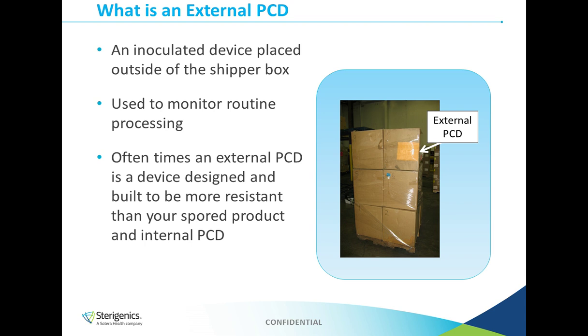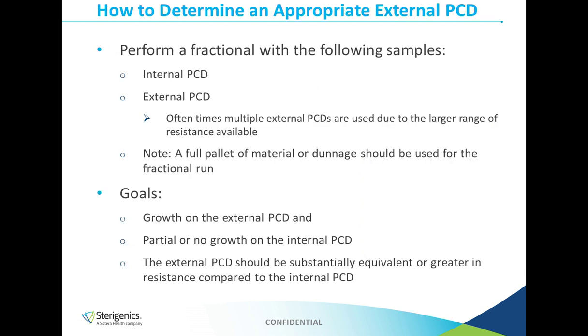You're also not sending your own product in for testing, so you're not losing product that could have been released. Now oftentimes an external PCD is a device that's designed or built to be more resistant than your spored product or your internal PCD, such as a test pack. Now how do you determine which PCD is appropriate? Again, you're going to want to perform a fractional run, and on this run you're going to include the internal PCD and an external PCD. Oftentimes multiple external PCDs are used, and this is because they provide a wider range of resistance, so you're more likely to find the test pack that correlates best with that internal PCD.